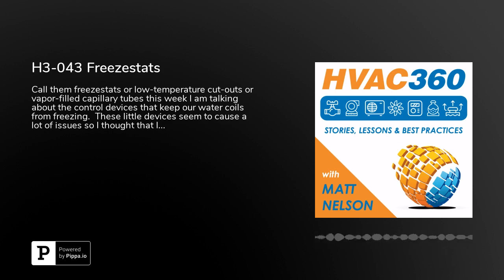So the way you're supposed to design these things, the coverage goes that 1 linear foot of this Freezestat covers approximately 1 square foot of coil. If you extrapolate the math here, these capillary tubes typically come in 20-foot lengths. There are also options for smaller ones. Some manufacturers sell them in 10-foot lengths. Some actually have 6-foot lengths. So it depends on what manufacturer you're dealing with. Those are 3 of the common lengths that you can get for these things. But so you have a 1 linear foot to 1 square foot ratio.